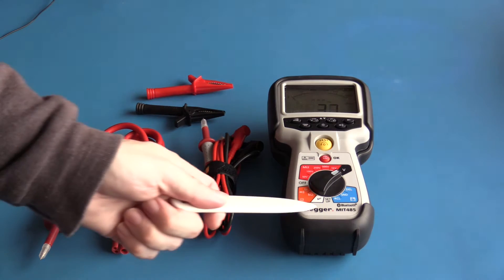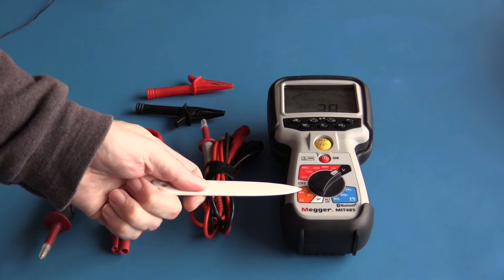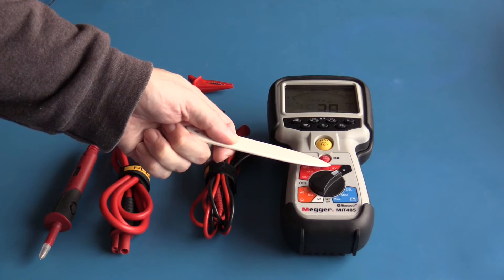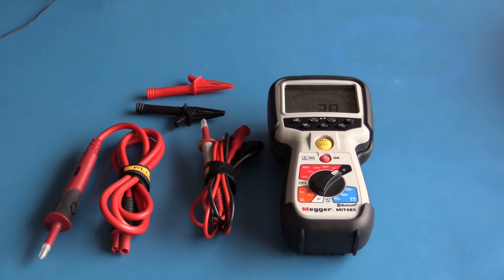Its measurement functions are capacitance, resistance up to 1 megaohm, continuity, 50V through to 1000V insulation resistance testing, and a dedicated voltage measurement mode. This meter can also do time, dielectric absorption ratio, as well as polarization index measurements.